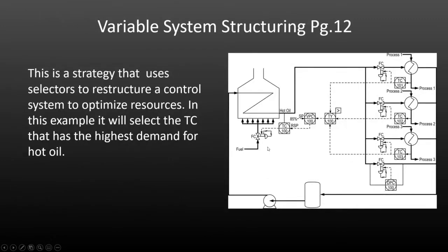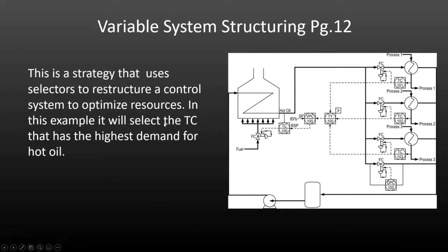The last application is variable system structuring — a strategy that uses selectors to restructure a control system in order to optimize resources. In this case, the resource is hot oil and how it's applied to exchangers based on demand. The selector here is a high selector, allocating hot oil to whichever exchanger has the highest demand based on the process variable of temperature. The most common applications are probably the safety override versions and the redundant ones — you'll see a lot of redundancy especially in larger petrochemical facilities.